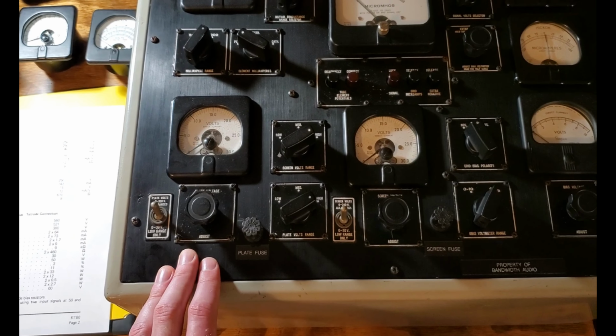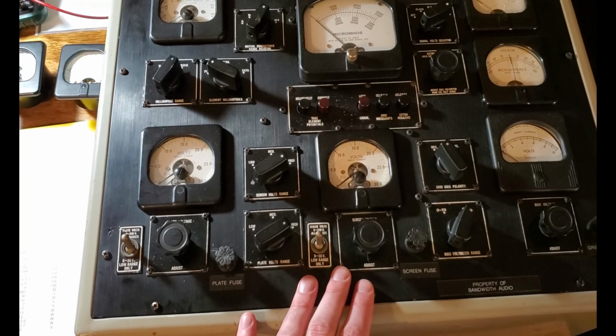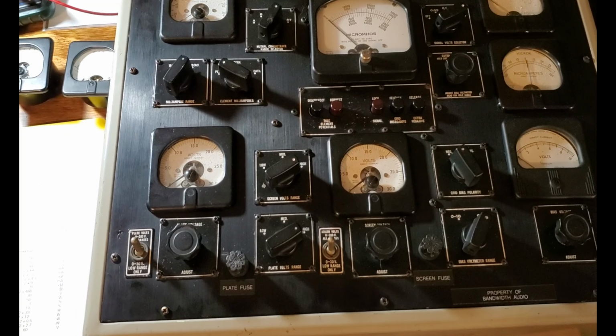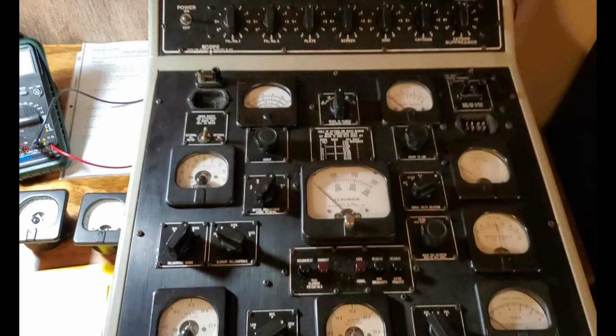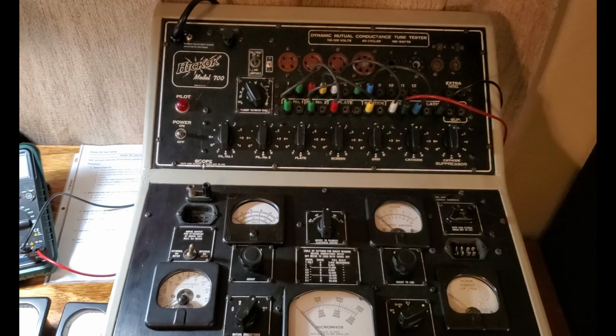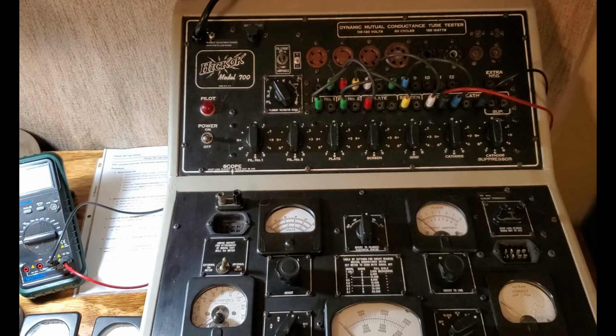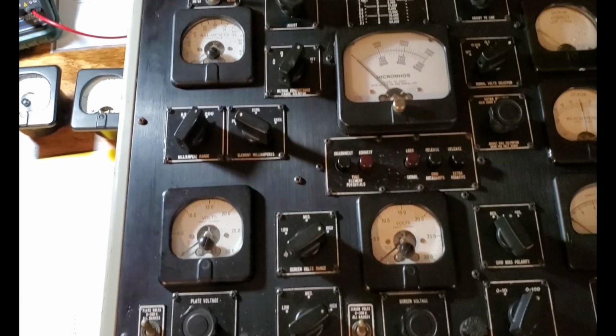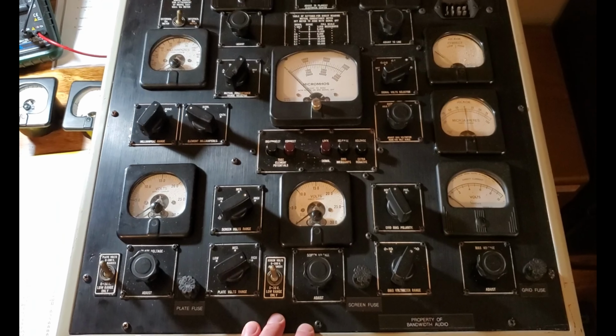And that's really nice because once you set this up for a specific vacuum tube and you put a tube in the patch panel up here, you don't need to adjust any of these knobs once you get your test conditions set up, even if the tube performance is wildly different. And wildly different all the way from an open circuit to the full 200 milliamp scale that this can measure. So that's extremely nice with this tester and makes it super repeatable. We've had great repeatability results with something that's old and analog like this.